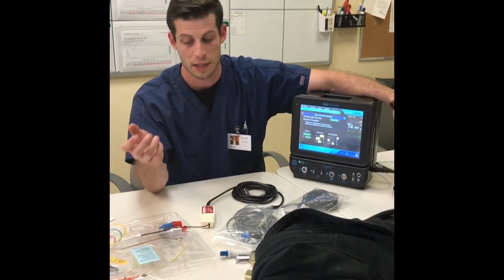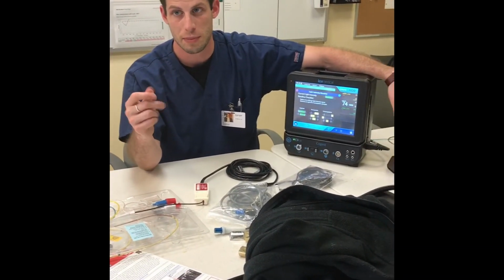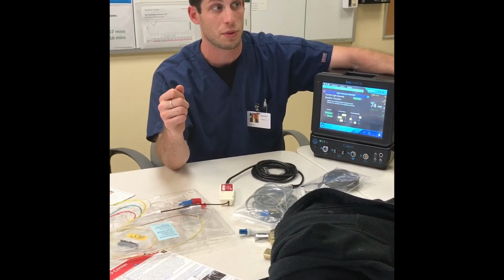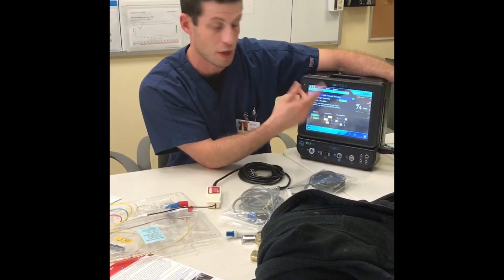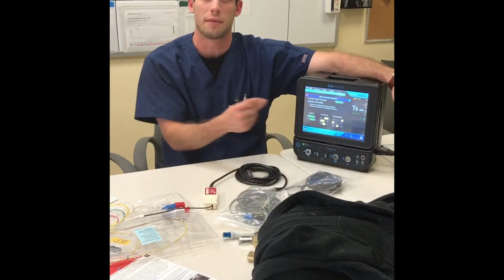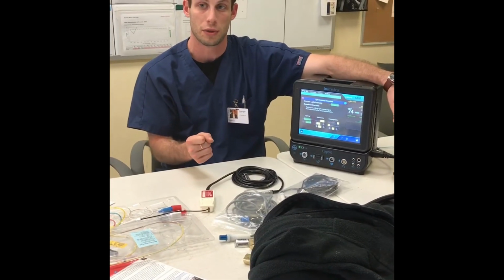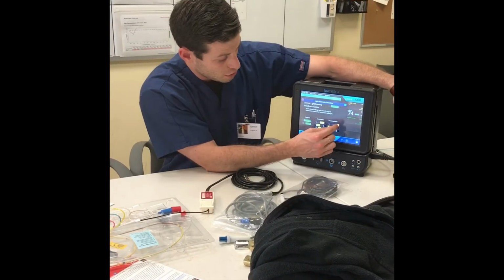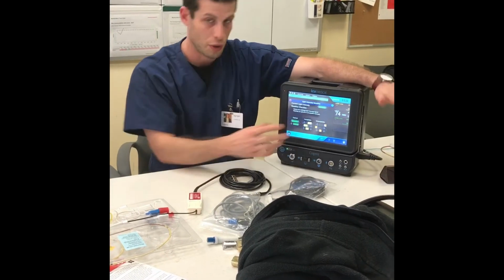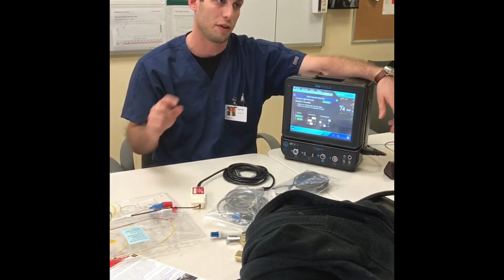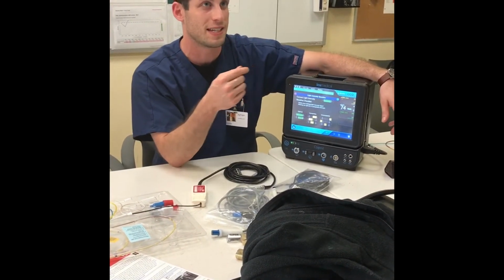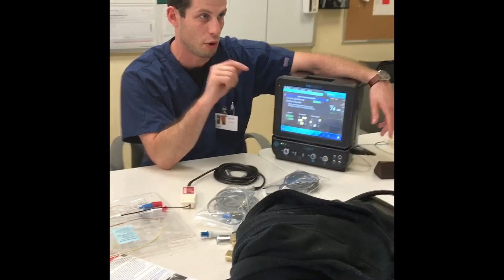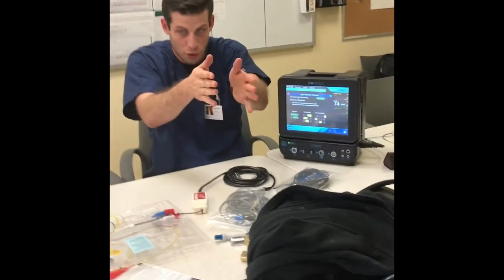These are very invasive lines. Fast flush with the PA. That many times will clear it, and you can then go in, do another light intensity baseline, and you should see that immediately either come back to yellow or green. If it goes this direction, high, only one thing really does that. The catheter took a little turn and is now facing the tissue, the inside of the pulmonary artery. So it's not facing down at flowing blood, it's sitting right on a wall.